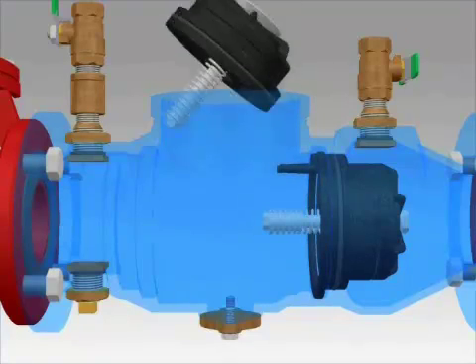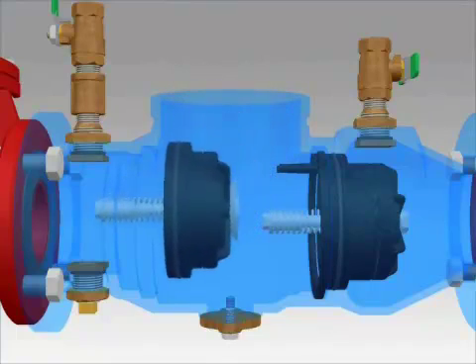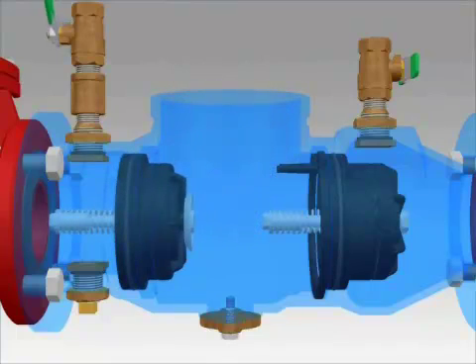Install the number 1 check in the body and close the number 2 test cock to hold the check in place. If the valve was not drained, water may squirt from the number 2 test cock as the check is installed.